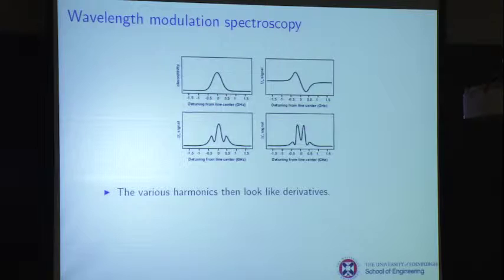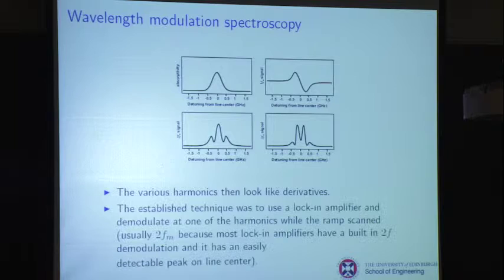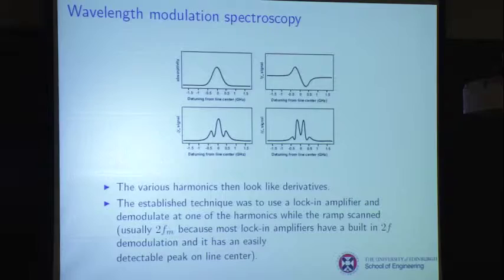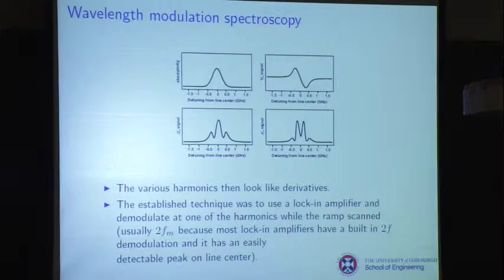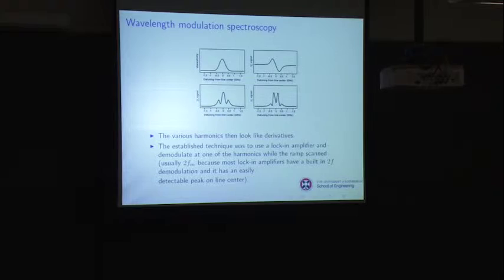Here are the derivative signals: the absorptivity at frequency zero is just the scan, the 1f signal is the first derivative, the 2f signal is the second derivative, the 3f, and so on. The old-fashioned technique was to use a lock-in amplifier demodulating at the 2f harmonic while the ramp scanned — people used 2f because there was literally a 2f button on lock-in amplifiers. What came out as you slow-scanned was the second derivative of the Voigt profile, which required pages of Fourier series modeling to extract concentrations.